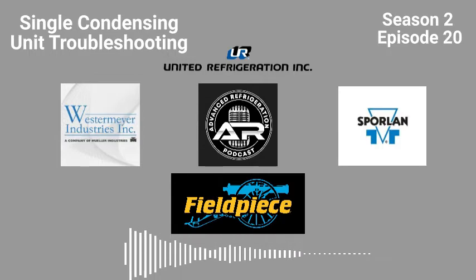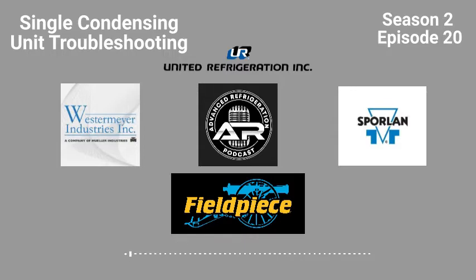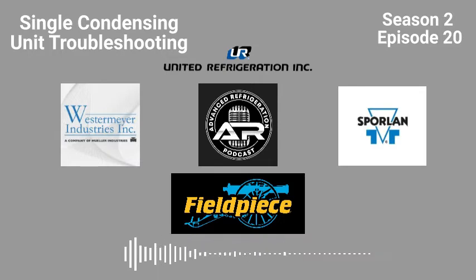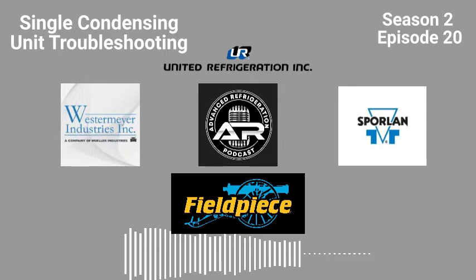I just want to throw this out here. I see this much worse with pulse valves. Remember that Amazon store? That was pulse valves. Yes. With SCR valves, it doesn't seem to pop up as much, and same thing with the standard TXVs, because I've done the same units. I don't have pulse valves on any of ours, but we have X-Line units, and they're not as oversized. They're a lot closer. We're running like a plus 13 degree evaporator, but we never make superheat. We don't even get enough runtime to make superheat.